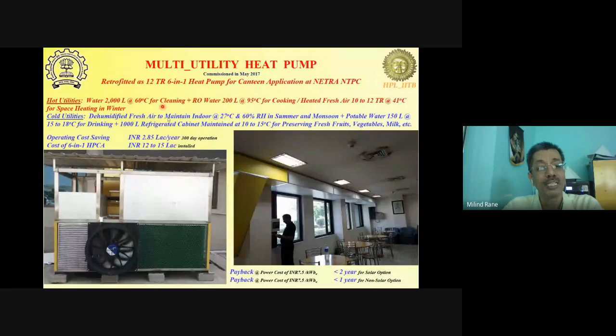And while the compressor operated for 6 to 7 hours a day, 2 hours in the morning during breakfast period, 3 hours during lunchtime, and 1.5 hours during the evening during different times, this unit could recover and store around 200 liters of hot water, and it could deliver 2,000 liters of hot water at 60 degrees centigrade for cleaning and sanitation purpose. So the RO water, it could heat up 200 liters of RO water right up to 90-95 degrees centigrade and this could be directly used for cooking.